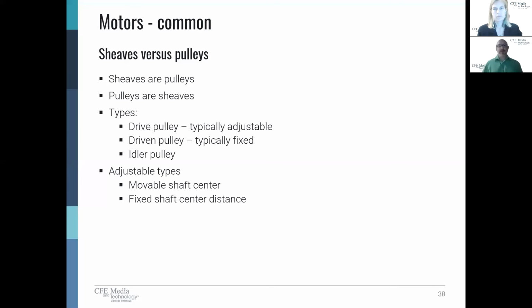Why would we do that? Well, if we want to change the speed of that fan for balancing, for example, then we can do that by simply changing the operational diameter. We can pull it apart and allow the belt to sit more in the groove, or we can push it together and make the belt sit more on the top side. So we can change the operational diameter of that pulley. And we can change motor speed by using VFDs or other methods, but those are expensive. If I have an exhaust fan, for example, I might want to just be able to have a fixed flow, but then I have to balance it. So engineers can consider that an adjustable sheave or an adjustable pulley will give them some tunability when it comes time to actually balancing.